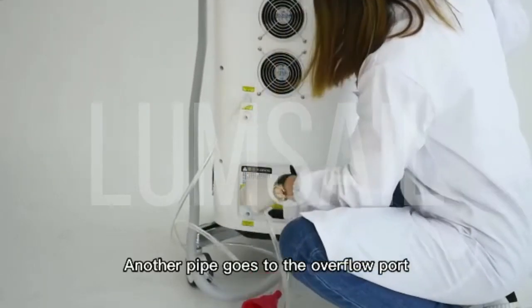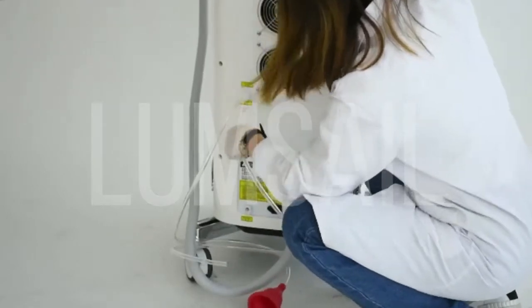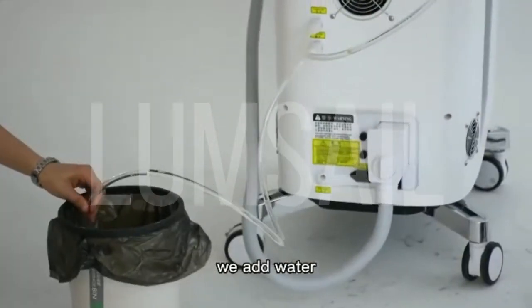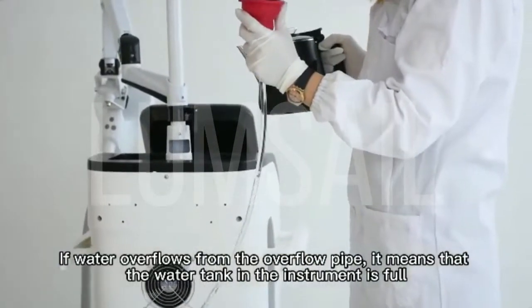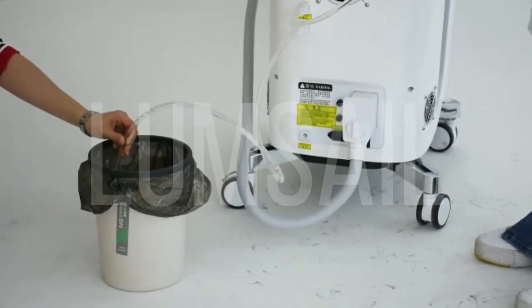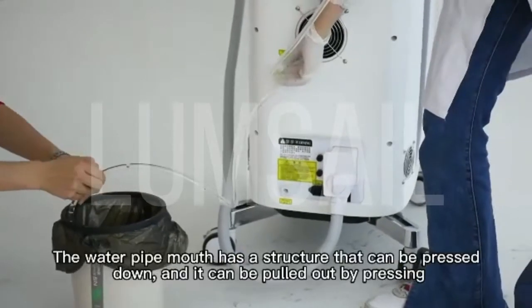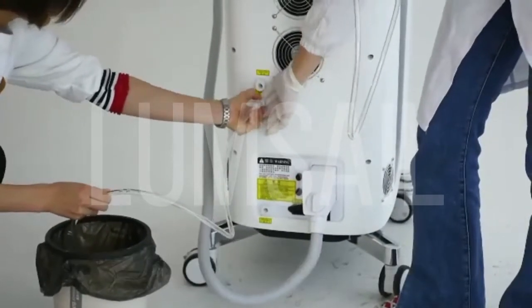Another pipe goes to the overflow port. In order to prevent water from overflowing, it can be caught by a trash can or a water basin, etc. We add water. If water overflows from the overflow pipe, it means that the water tank in the instrument is full. Then you can remove the tube. Now that the water has overflowed, we unplug the tube. The water pipe mouth has a structure that can be pressed down, and it can be pulled out by pressing.